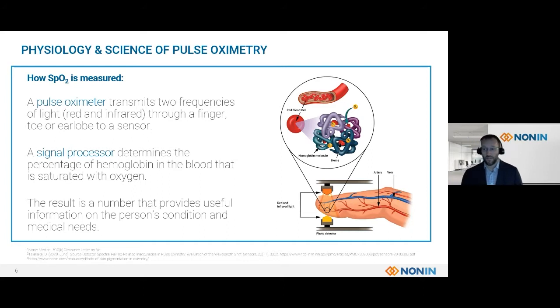So Nonin oximetry, as I've mentioned, really has that quality that we're known for. This is due to our 30+ years of experience in light sensing technology. When we first developed the pure light sensor technology, it provides only the purest red and infrared LEDs to produce high intensity pure light spectrums. And this has been shown to eliminate variations in readings for consistent measurements, especially at critical SpO2 levels. These high quality sensors also ensure the accuracy is not degraded due to skin pigmentation or low perfusion.